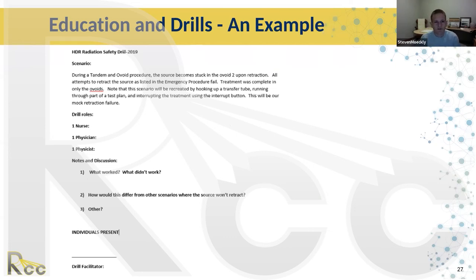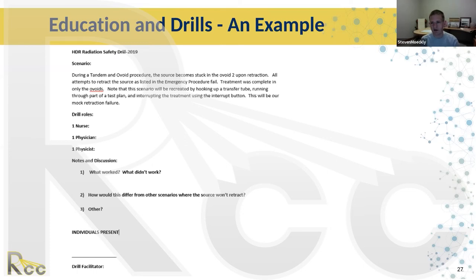Here's an example drill we developed — it takes about 20 minutes. During a tandem and ovoid procedure, the source becomes stuck in the ovoid 2 upon retraction. All attempts to retract the source using the emergency procedure fail. The treatment was complete only in the ovoids — I know that because I was watching the console at all times as the physicist. We recreate the scenario by hooking up a transfer tube, running through part of a plan, and interrupting the treatment using the interrupt button. The drill involves roles for a nurse, physician, and physicist. Afterward, we discuss what worked, what didn't, and then document who was present.